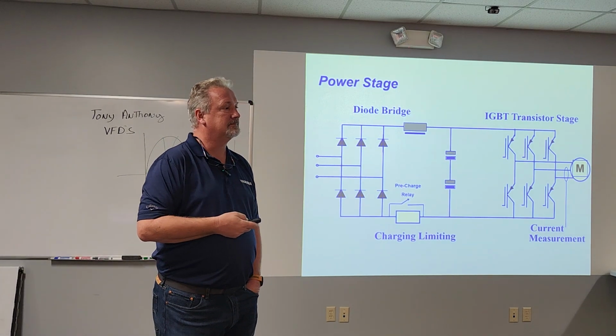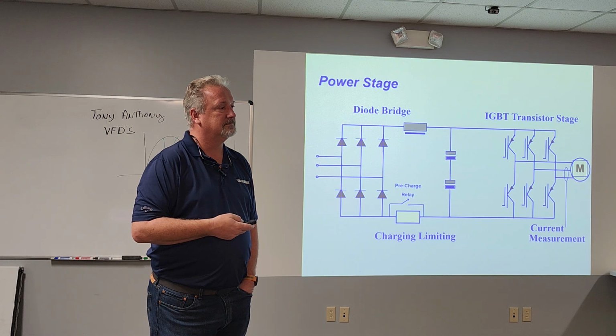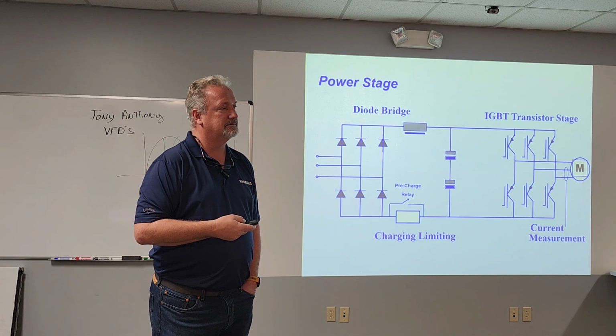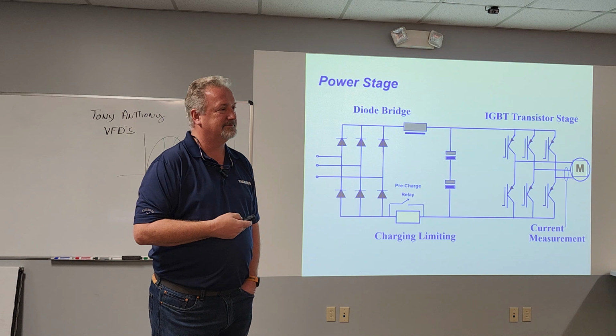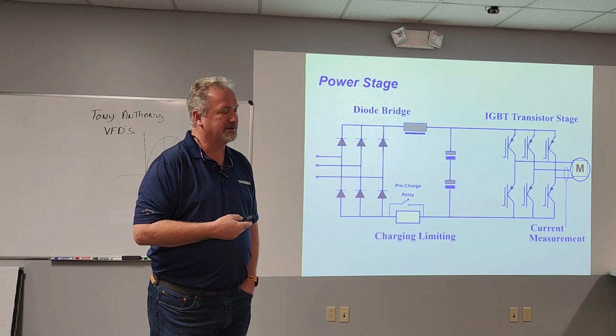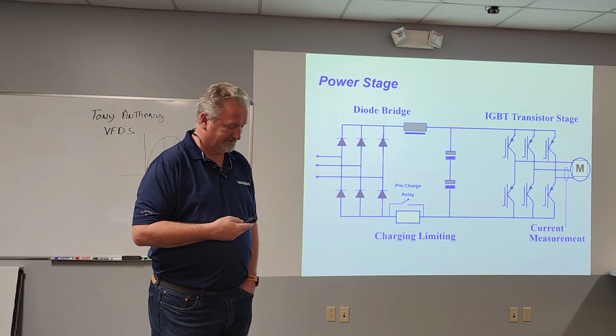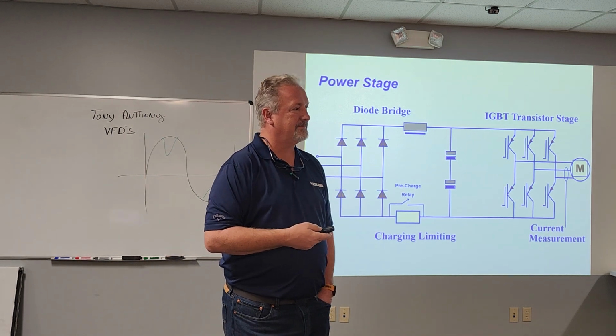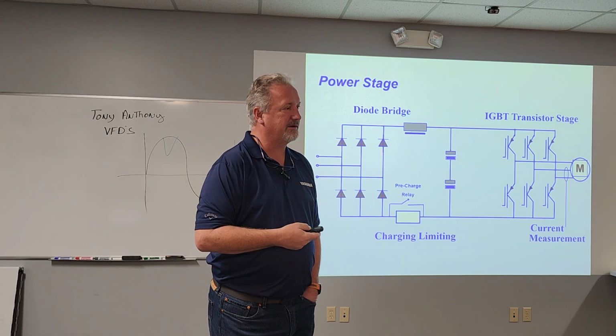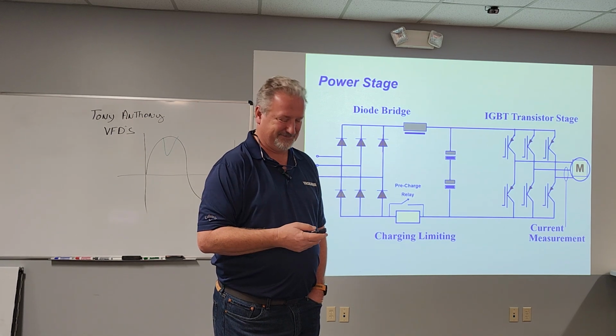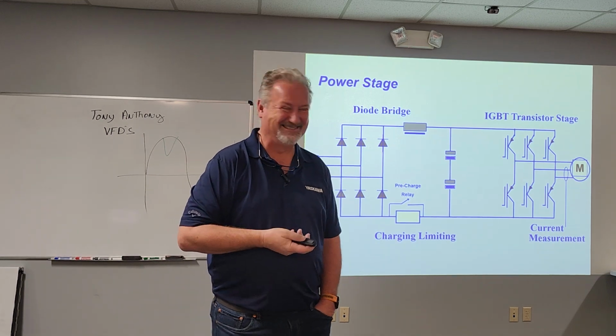Well, one question I always ask electricians or HVAC people, what 2 things determine the speed of an alternating current motor? Number of poles and frequency. They always say number of poles and voltage. So if you have a 120 volt motor and you hook it up mistakenly to 230, you think it's going to run twice as fast. No, it's not. It's 60 hertz. It's going to have twice as much current because you have 240 pushing the stuff through it instead of 120, but it's not going to go twice as fast. It's frequency and the number of poles on the motor. It's going to burn it up. Twice as much smoke for half the time.